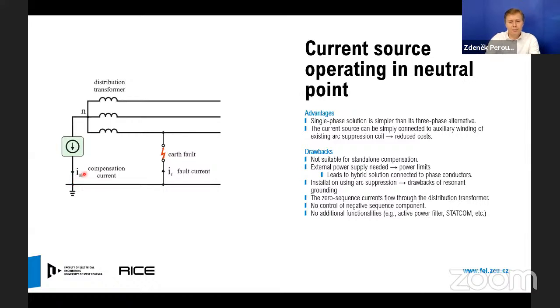It is definitely a very cheap solution, and the current source can be simply connected to the auxiliary winding of an existing arc suppression coil, and in this way we do not need to put any transformer into the system, and it leads to a further cost reduction. On the other hand, there are plenty of drawbacks of this location of the active current source compensating the fault current. This solution is not suitable for standalone compensation because we need an external power supply, and it also brings us quite strict power limits.